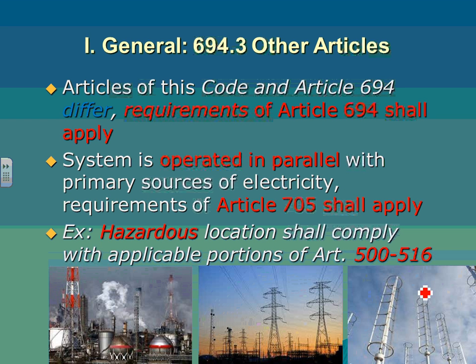Every time you bring a system in parallel with a prime source of power, you have to adhere to Article 705. Long story short, this will tell you that you have to have a means of identifying the second source of power to the building, number one. And of course, you have to have a means of isolating the power. That power has to be isolated upon the failure of the grid, because you don't want to kill electricians. So the anti-islanding comes directly from 705, for the solar photovoltaic system as well as for the wind.